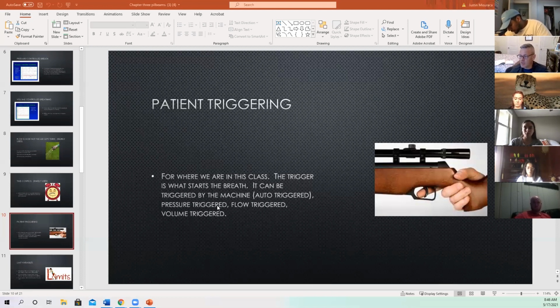Okay. There's another type of triggering. There was volume triggering that we used to use, and nobody uses it anymore. But there's a new one that's been out. I shouldn't say new. It's been out probably like 8-10 years. And it's called NAVA. Does anybody know what NAVA is? It is an electrical signal that's coming from your phrenic nerve. So we drop an NG tube down and we sit that sensor right at your phrenic nerve, right at your diaphragm. And that senses a millivolt change, and the millivolt change will trigger the ventilator. So when the patient has a signal from their brain that goes to the phrenic nerve, the ventilator cycles instantaneously, way faster than any other mode of triggering that's out there. That's pretty neat, isn't it?